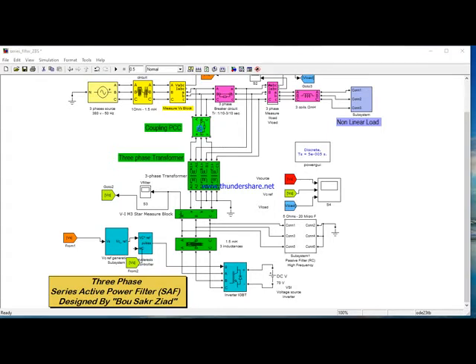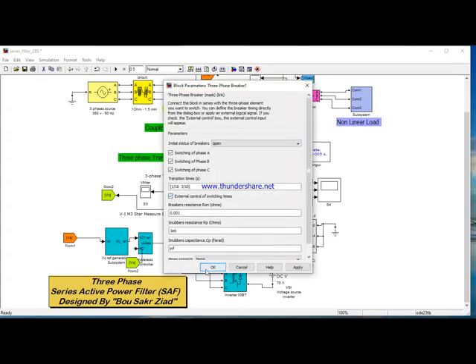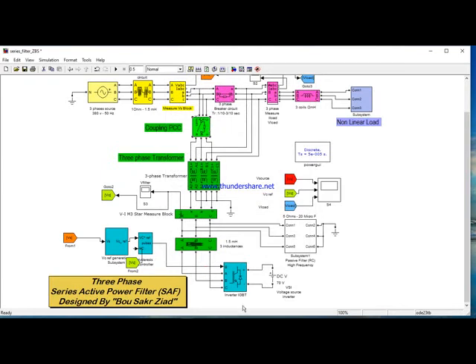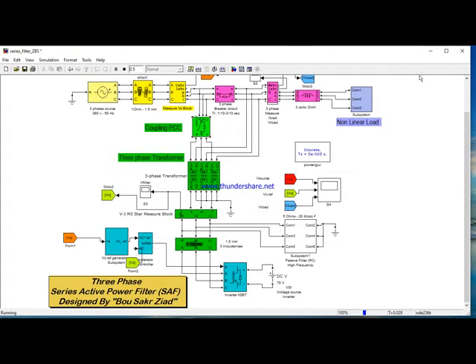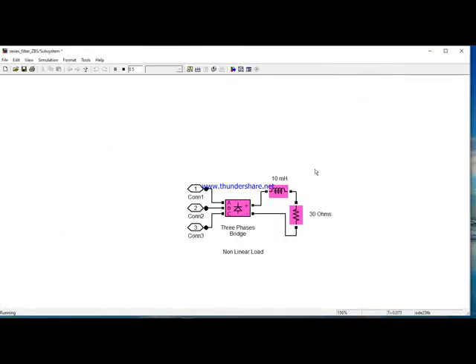Now I want to show you what happens without the filter. I want to eliminate the setup effect of the breaker circuit and run the simulation. The nonlinear load is constituted by a 3-phase bridge with a resistance of 30 ohms. This nonlinear load has an effect on the source and load, producing harmonics and increasing the THD — or total harmonic distortion.